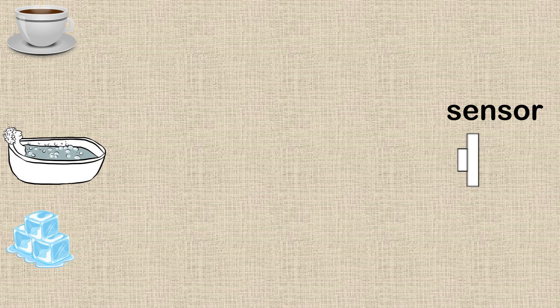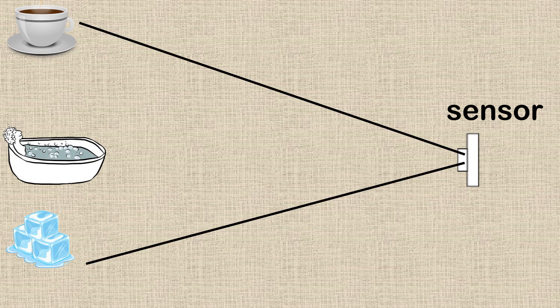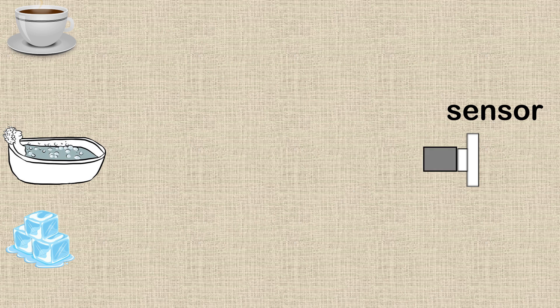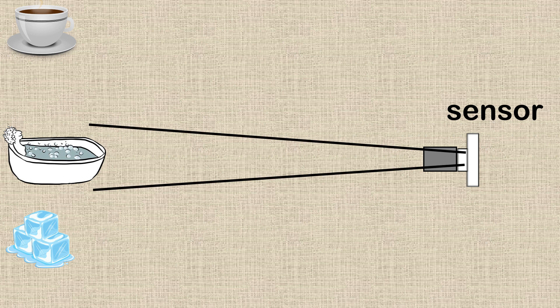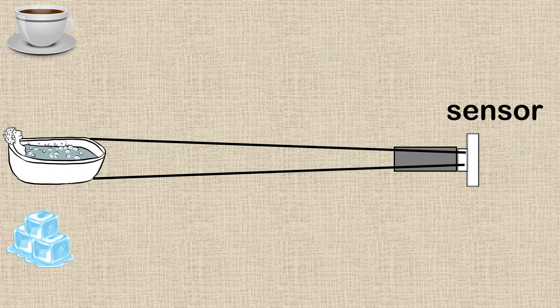If we look at the one without a shroud, you can see that it can accept temperatures or it's sensing the temperature of a wide range, and the further away from whatever it is you're trying to measure the temperature of, then the more it's taking up the temperature from other objects, sort of like an average going on. If you have a shroud on, then you can see that the beam becomes narrowed.